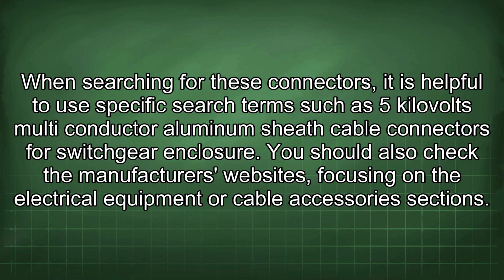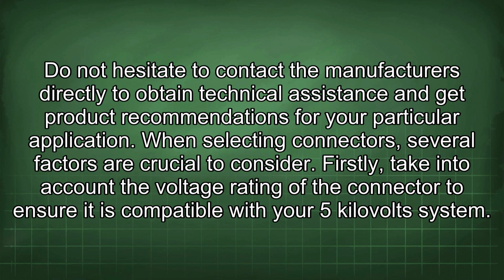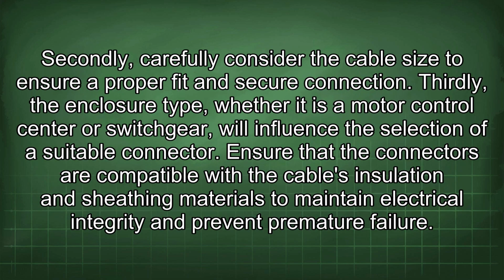You should also check the manufacturer's websites, focusing on the electrical equipment or cable accessories sections. Do not hesitate to contact the manufacturers directly to obtain technical assistance and get product recommendations for your particular application. When selecting connectors, several factors are crucial to consider. Firstly, take into account the voltage rating of the connector to ensure it is compatible with your 5 kV system. Secondly, carefully consider the cable size to ensure a proper fit and secure connection.